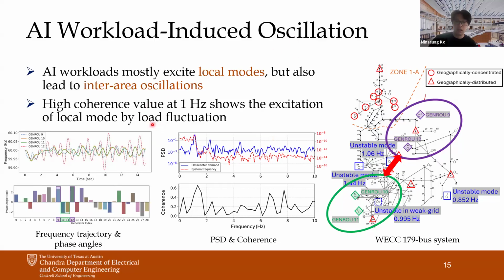As you can see from the left figure, there is a sustained forced oscillation at 1 Hertz. But an interesting point of this AI workload-induced oscillation is that although it is at the local mode frequency, it shows behaviors like inter-area oscillations. When we look at the frequency trajectories in the purple zone and the green zone, you can see that they have opposite phase angles. So there are behaviors like inter-area oscillations.